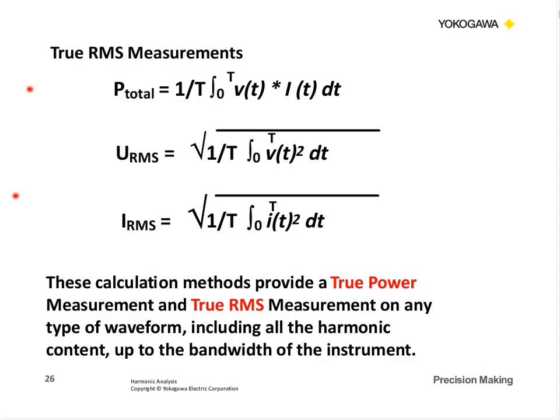So for true RMS measurements, again, the power is the instantaneous voltage times the instantaneous current, multiplied together, accumulated over some time period, multiplied by 1 over t. And we know the RMS, the root mean square function of voltage and current, where again we take the digitized value of voltage, accumulate them over some time period as squared, and then we integrate that, multiply by 1 over t and take the square root of it. So that's your formula for RMS, root mean square.